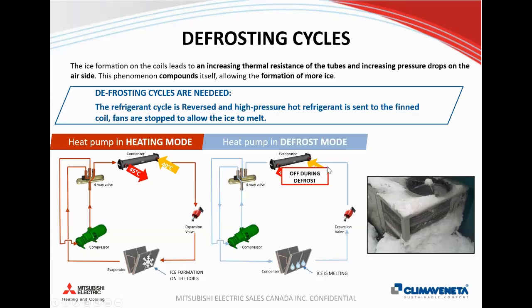We shut off water flow from the condenser because if our building's in heating mode, we don't want to be cooling the water down in that system. That's counterintuitive to the concept of a heat pump. So we shut off the water flow to the indoor spaces. And we also are now sending hot refrigerant to the condenser coil on the machine, but we're also shutting off the fans. And this is to allow the refrigerant, hot gas, to melt any ice or frost on the exterior of that coil. So typically with defrost, there's kind of two main ways most manufacturers are doing it.